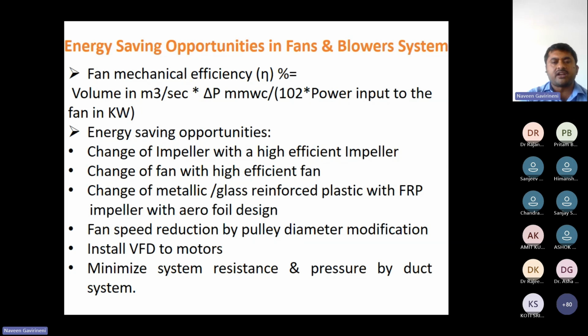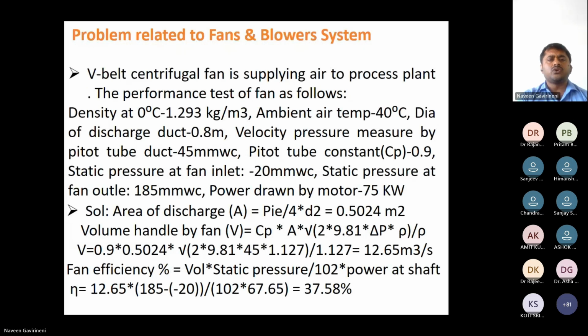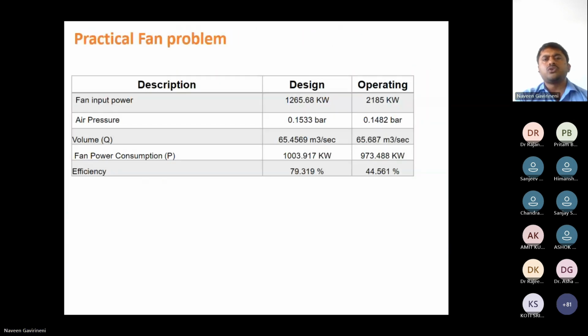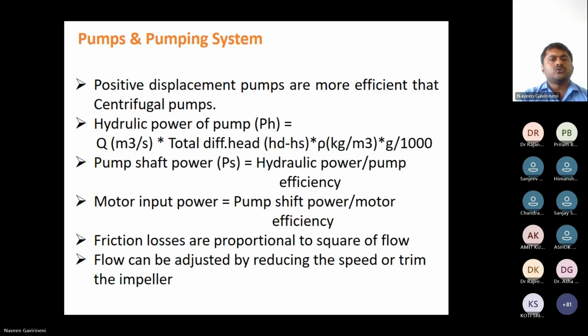Fan speed reduction by pulley diameter modification. VFDs also play a vital role in reducing power consumption. Minimize the system resistance and pressure drop in the duct system. So this is the problem. As I explained the formula and all the things, this is the example problem. Just go through that while sharing the presentation. So this is the result. They have given 79% design efficiency. We are getting 44 due to some problems. Some leakages are there, blow leakage and all the things. After that we are going to segregate them now.